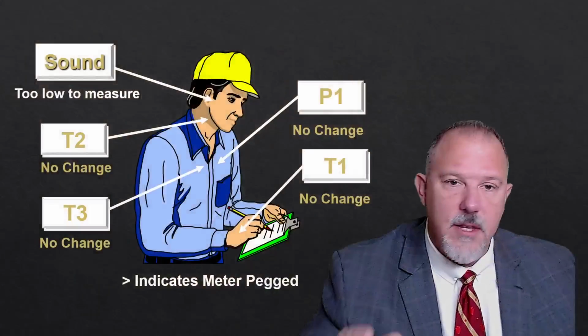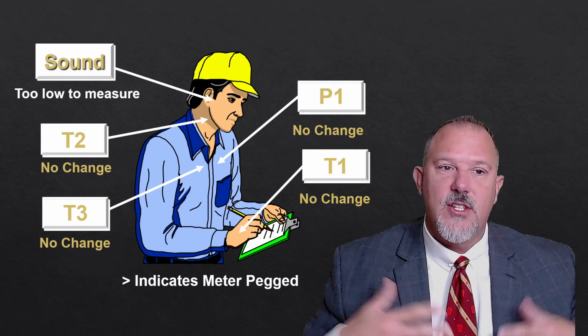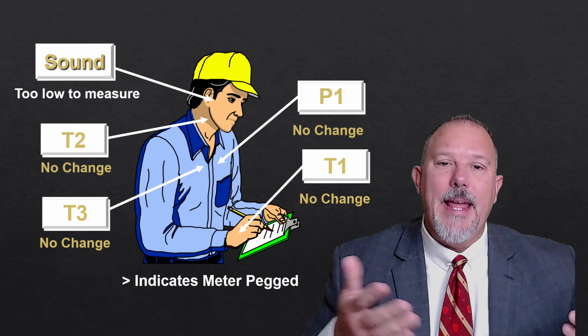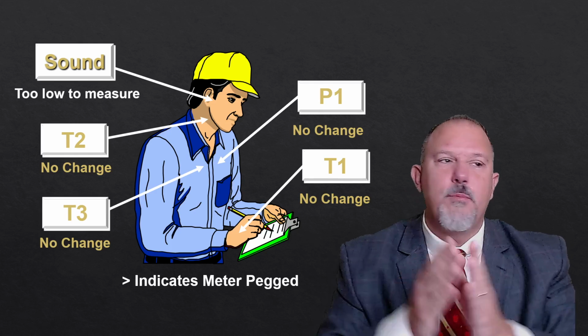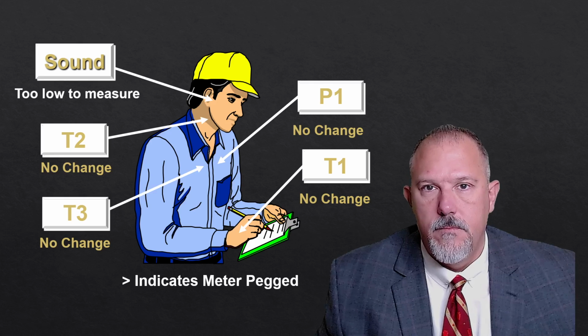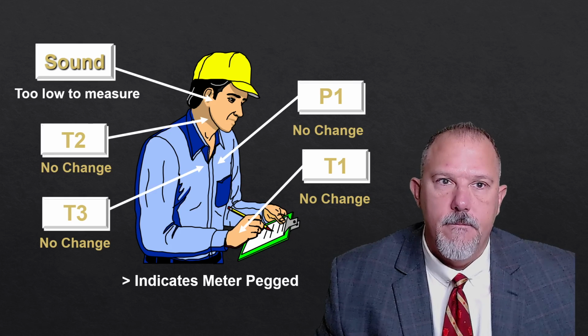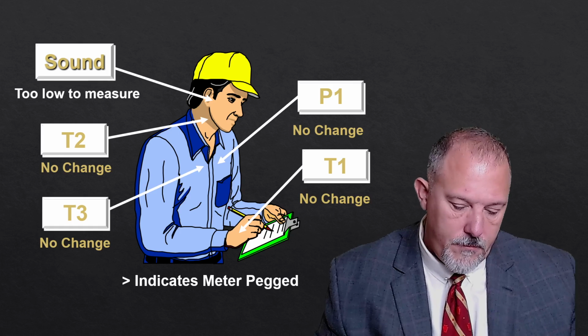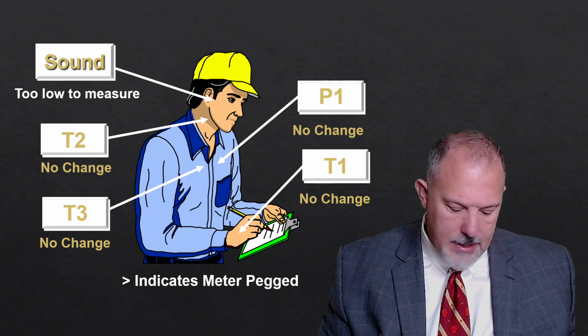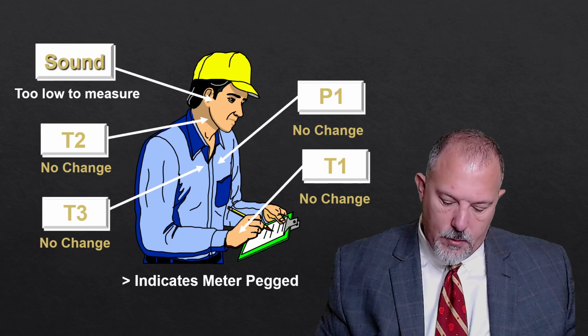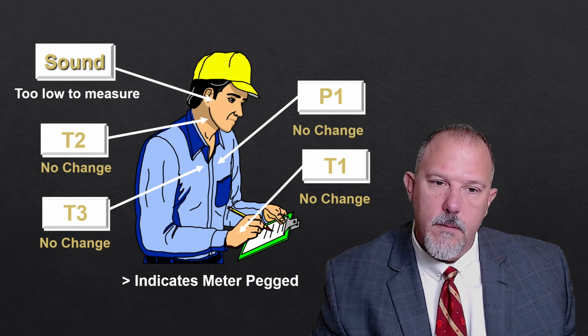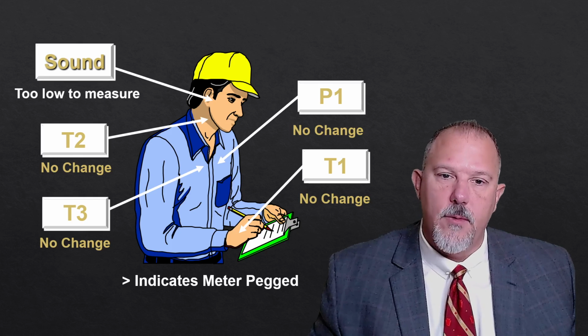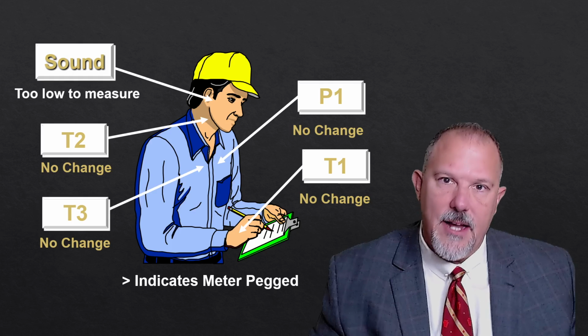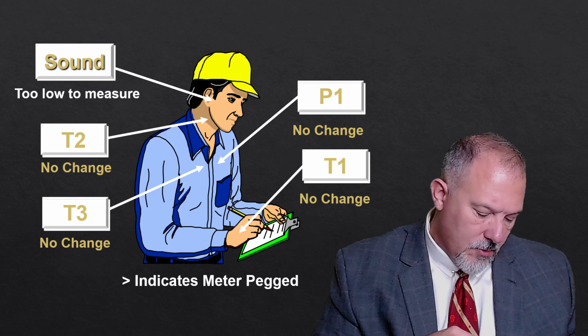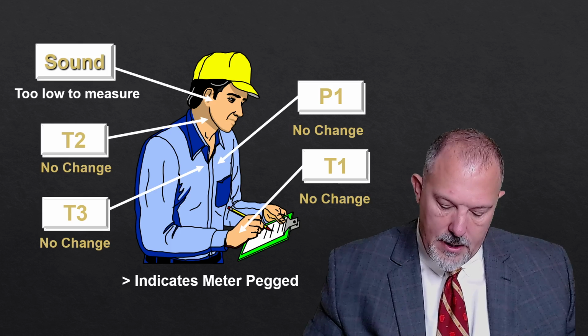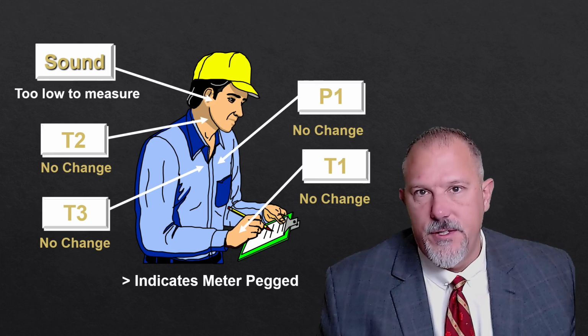Now, if I look at the statistics, I got no temperature change. The sound was too low to measure. I got no change even on the hands who were right there. That arc flash boundary is probably millimeters, to a point where you're getting into a shock hazard as opposed to an arc flash hazard. The incident energy on that one was less than 0.17. The previous one was 0.34, and this one was 0.17. I don't know if I got those backwards. This was less than 0.17 calories per centimeter squared. The previous one was around 0.34. And the arc flash boundary on this one was 5 inches.